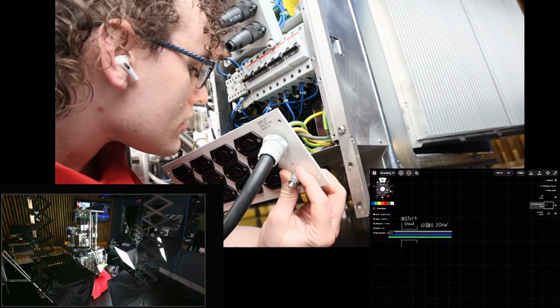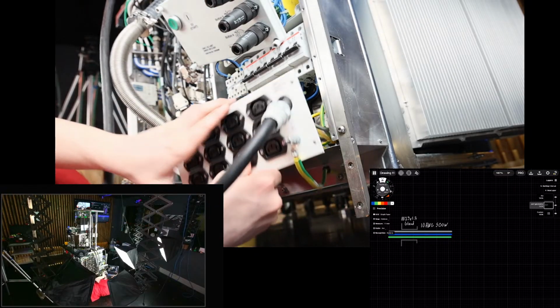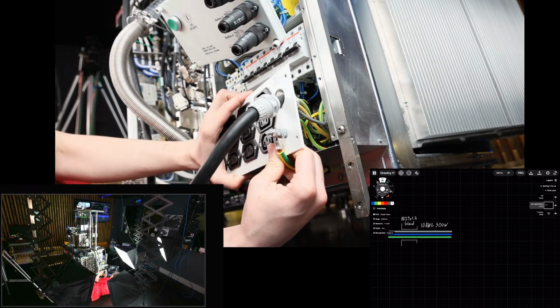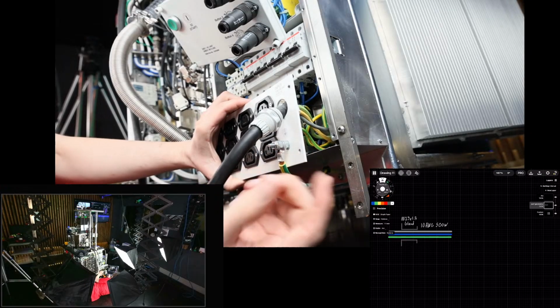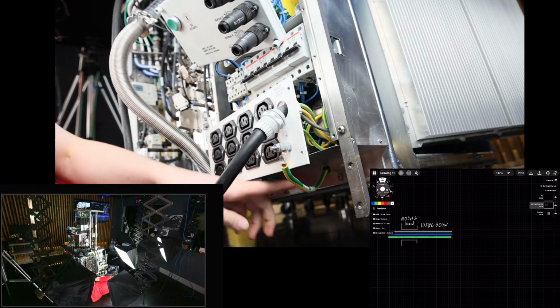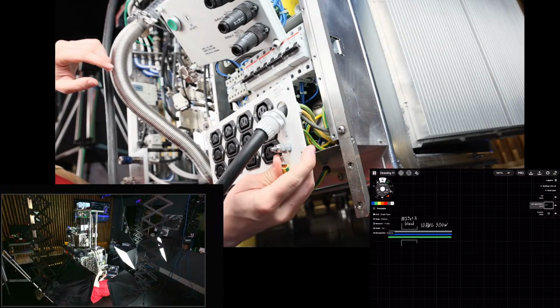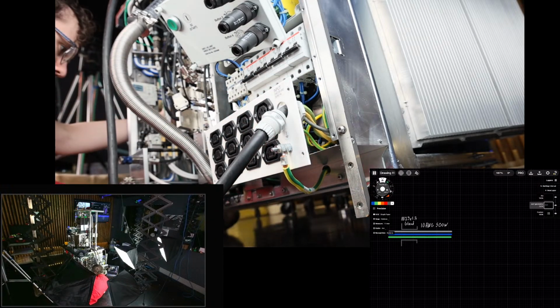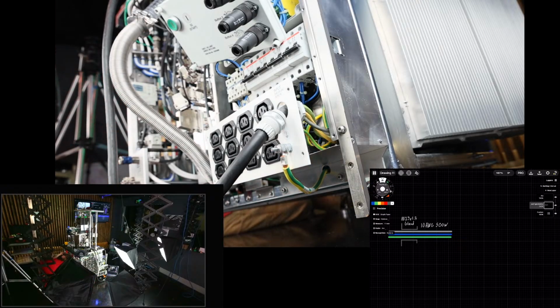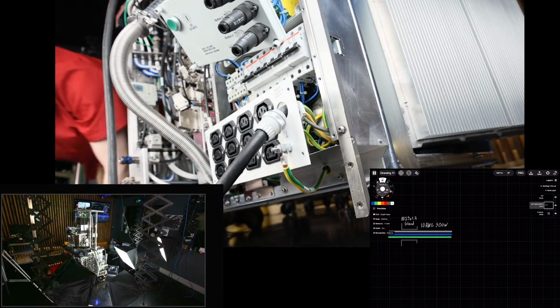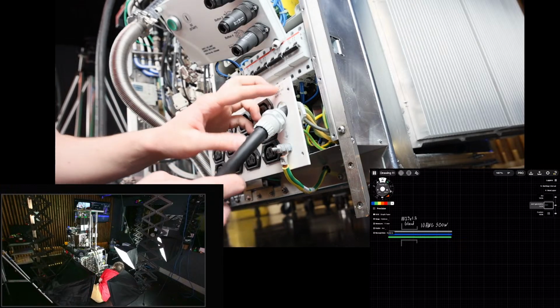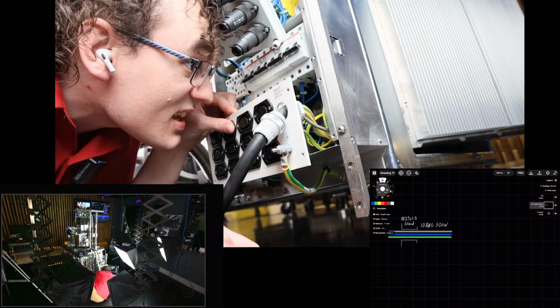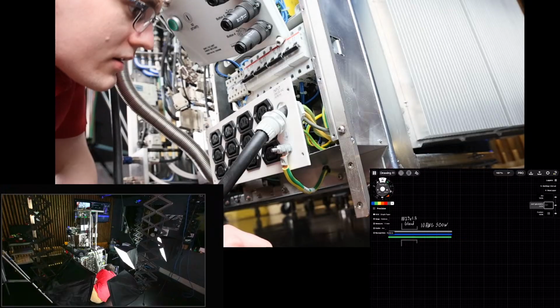No. Well, no, there is a cable. Okay, here's the deal. You see this cable. So there's front and back on this panel. We got a cable that goes to the back of this ring terminal, or lug, nut, bolt, and a cable that comes from the front of it. And I bet that this cable then goes to the front of my frame here. So that makes more sense to me. I would have been very surprised if they didn't have a cable connection that actually went to ground, you know? Yep, that cable does come up to our main grounds up here. So I like that a lot. Well, I have some thoughts, because it's interesting that we ended up with like three different ground ring terminals in here.